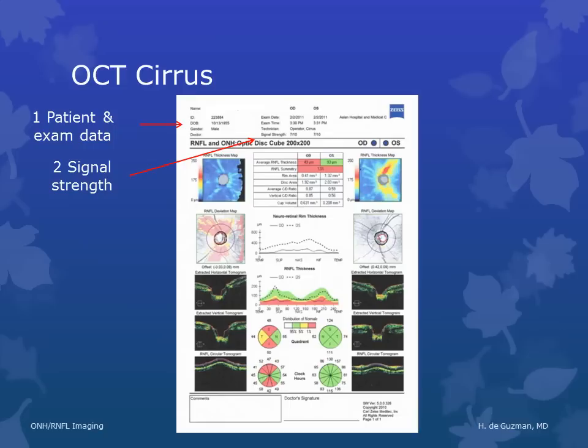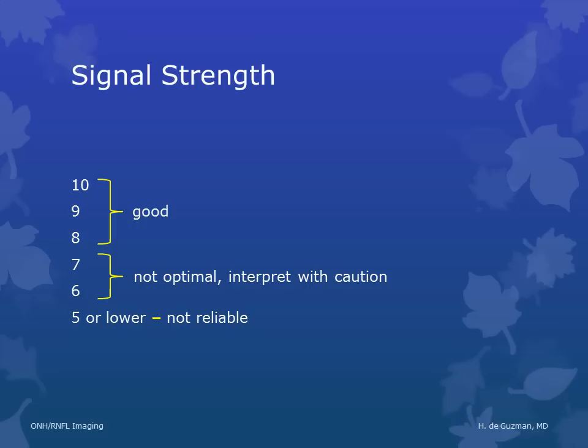Signal strength of 8, 9, or 10 are good. 6 and 7 are not optimal, but you might still be able to use those results — just interpret them with caution. A signal strength of 5 or lower is not reliable.